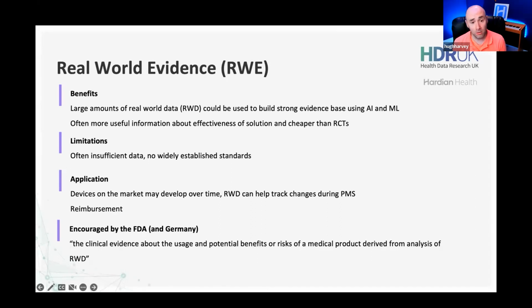That's a really good question, quite a niche specialty case, but in essence, you would have to put it in your post-market clinical follow-up for ongoing monitoring. So let's say you've implanted a device for the purposes of a clinical investigation, you've got regulatory approval, those devices remain implanted in patients. You absolutely, by law, have to follow those patients up ongoing for the lifetime of that device until they may be removed or the patient dies, I would assume.